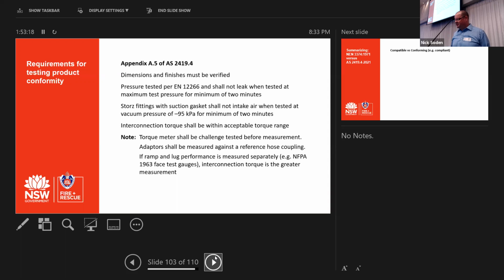The adapters shall be measured against a reference hose coupling. So we'll actually use a hose coupling when testing, because for those that don't know, the actual center bit of a hose coupling actually swivels, whereas what you see on a fire brigade booster or fire hydrant valve is static, and it just mates and it presses. It doesn't actually swivel when you turn the cam ring, it's actually static.